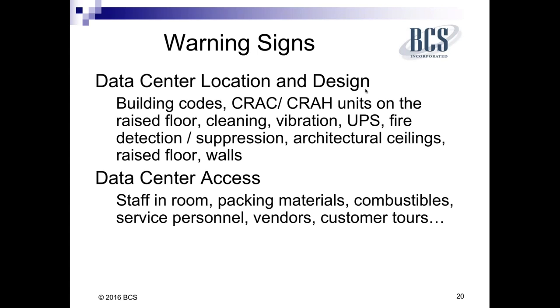Another thing to look at: access to the data center. Are you really proud of your data center and you take your customers and give them a tour? Do you still have people that have their work area in the critical environments? It's a machine room and an equipment room. It's not a work area. Do things get unpacked? Do you see any combustibles?